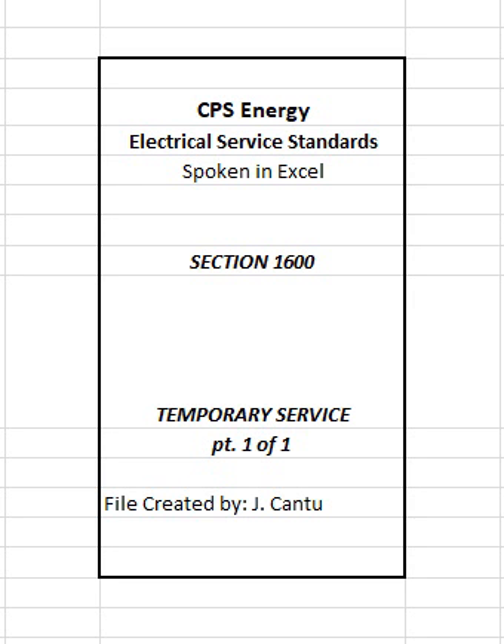Note 1. Where a secondary enclosure supplies a temporary meter loop, such loop shall not be installed closer than 3 feet to secondary enclosure. Section 1600, Temporary Service. Where installing a ground rod at the temporary meter structure location, customer shall not drive ground rod at an angle toward the side of the transformer or toward the front side of transformer. Customer shall be responsible for ensuring that ground rod installation will not cause damage to CPS Energy underground infrastructure.